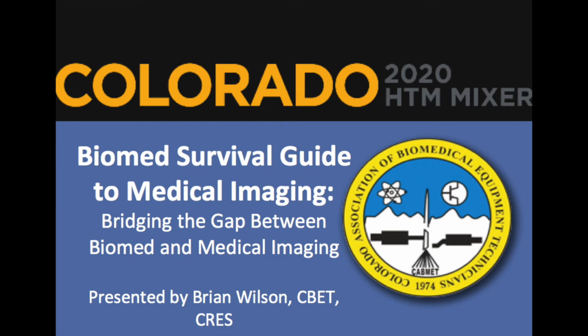Again, an advancement of PET scanners is the PET CT. What the PET CT will do is have your PET scanner on the front end, by where the pillow is on the scanner. As the patient's being scanned, they then go into the CT scanner on the backside, doing it all in one shot. This is due to the fact that the isotopes have a really short shelf life, so you have to do the scans almost immediately after administering them to the patient. But you get a better quality image and better spatial resolution in doing your diagnosis.